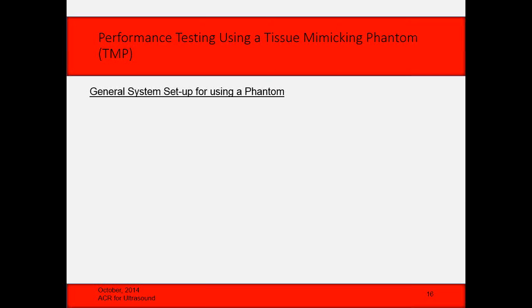So if you're using a tissue mimicking phantom, I have these general instructions for setting up and using a phantom. Basically, if you look at the phantom users manuals, most of them, except for the newer manuals from ATS, will tell you that you should set the system up for the best image quality. Well, you don't want to do that, because the phantoms aren't really good enough to test these things anymore anyway. And if you follow those instructions and turn on compound imaging and all the post-processing and all that stuff, it's going to hide problems, right? It's going to cover them up. So you'll only be able to detect massive failures, like the system doesn't boot up, almost that massive.